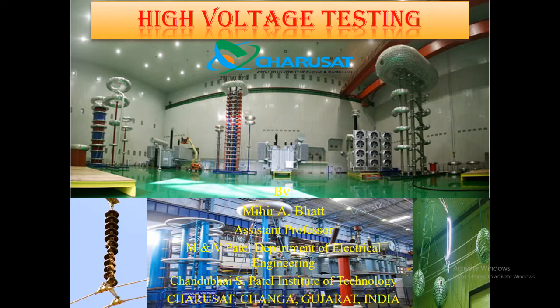That test is generally performed by following the test procedure suggested by either IEC 156 or IS 6792. So let us discuss how this breakdown voltage test is conducted on a liquid dielectric.